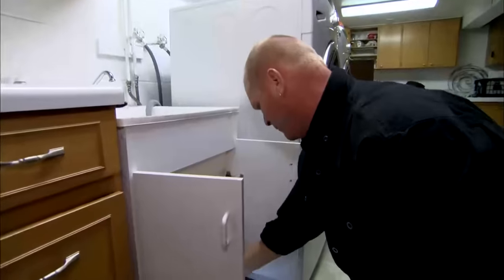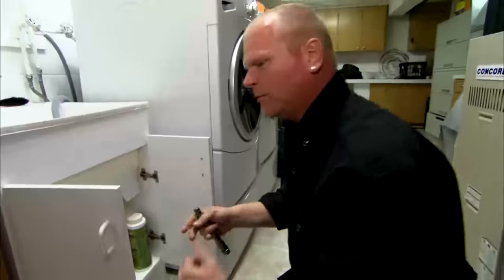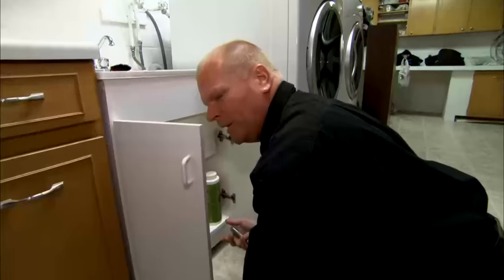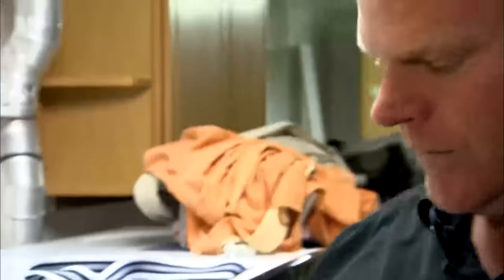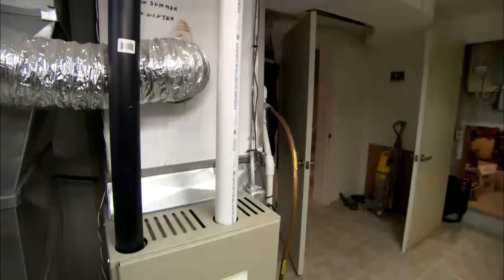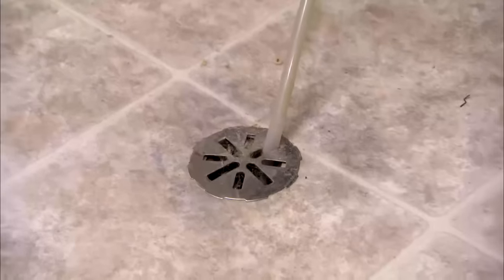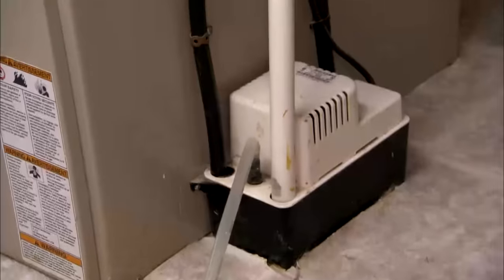Not the way to put in a laundry tub. This was not in the report. We have a beautiful laundry tub — but the drain is straight up with no trap that leads into what? It's a clay pipe that's in the floor. I think I can smell it — the methane gas coming out of the floor. That's going to be a pain. When you start adding things together, methane gas exhausting out of the drain, bringing it into the furnace, which should have been ducted outside for fresh air.